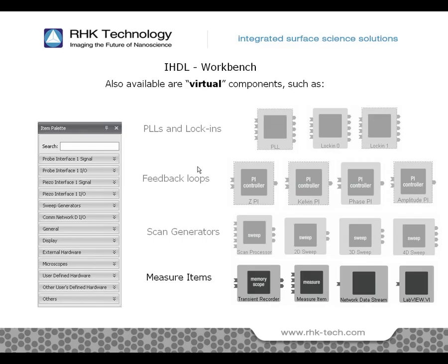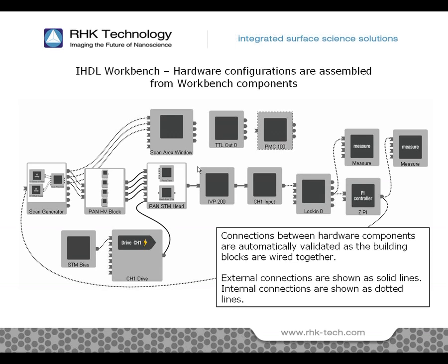So for customers that have an AFM that need a feedback loop for the Z topography, to do Kelvin force microscopy, for feedback off an interferometer for a quadrature lock, these can all be done simultaneously. To configure the controller, you simply select the components that are required and graphically connect them together. It's that easy. This example shows the setup of a basic STM. There are, of course, some basic rules that must be followed, but if you make a mistake, the software will alert you, show you what you did wrong, and not let you continue until you fix the mistake.